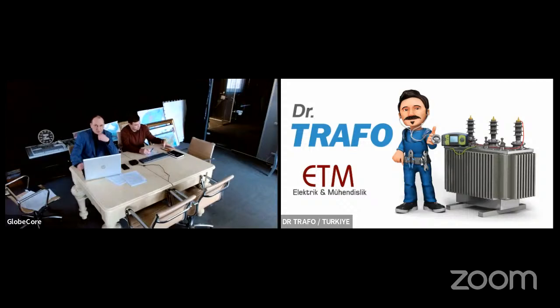Hi, sir. I was asking about TRO60. We already delivered 6 devices of it in Egypt. When I was delivering to the customer, he kept asking me, why should I enter the temperature every time I'm starting the test? The test is not going to start until I put in the temperature of the oil. He was asking why I should put in the temperature.